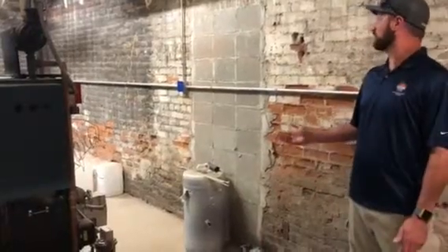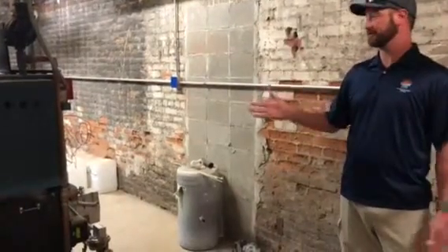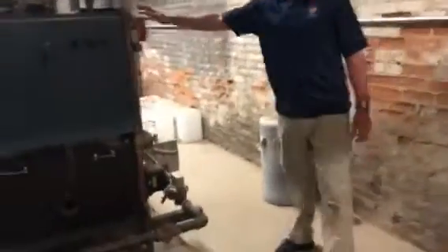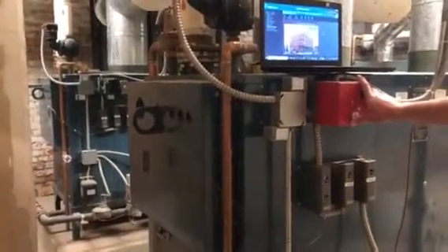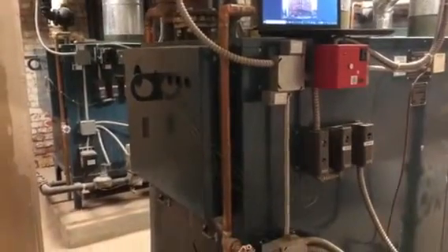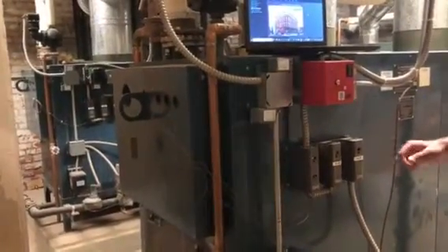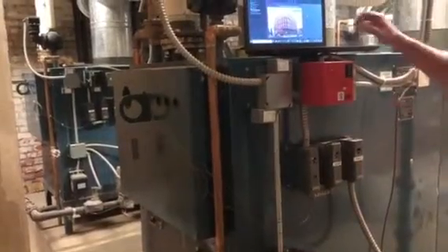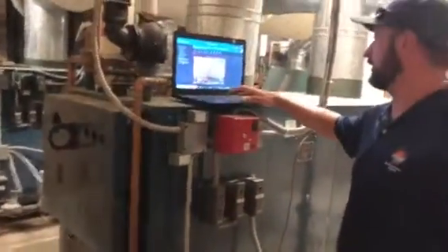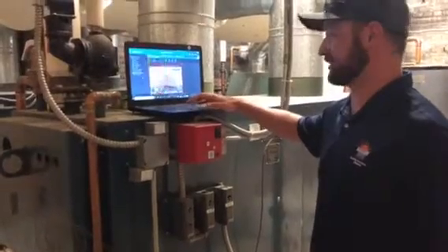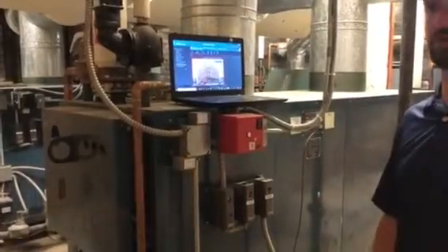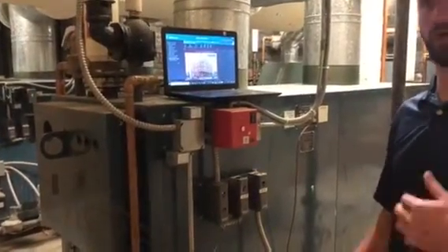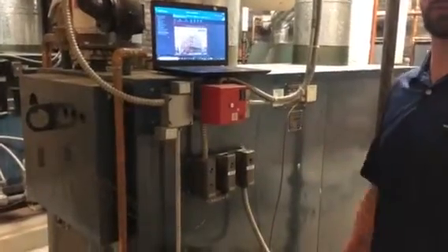What else are we doing? We've got temperature sensors. We have alarm contacts on the burner modules. So if this burner module goes into alarm, we'll generate an email alarm as well. Now, what's the lowest temperature on that controller as far as the lowest we can run the boiler? I believe we are programmed at 160. And we're also monitoring return temperature, so if our return drops too low, we're going to be trending that and making sure that we're not condensing the boilers.